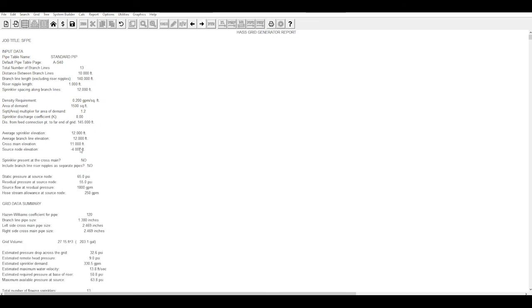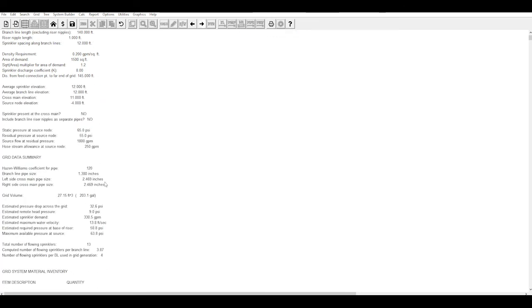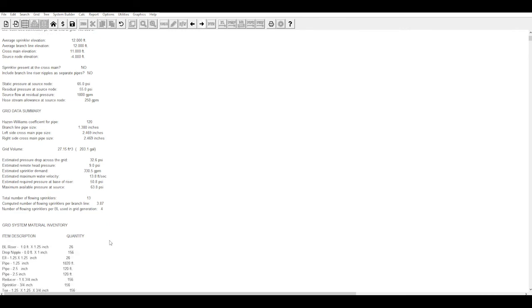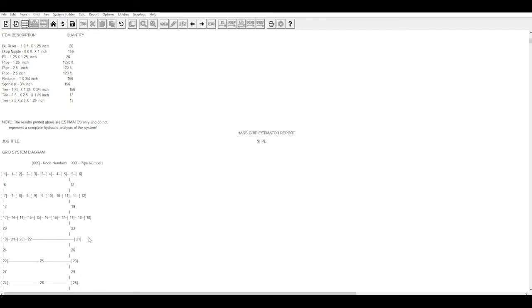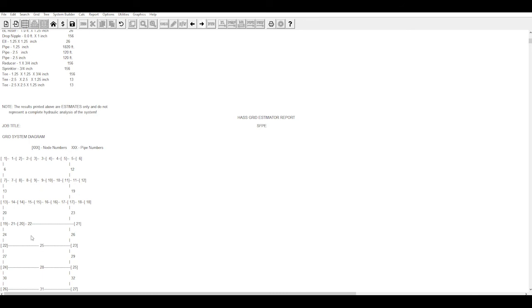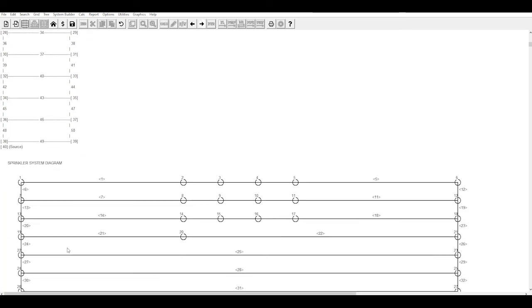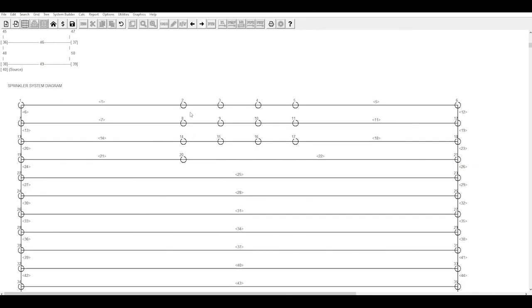So here's all that data that we entered. You can verify here again. The data that it's using to calculate. See here it also calculated out 13 sprinklers. 3.87 per branch line. So four per branch line. Then it gives you an item breakdown. And then we supply this little graph here. So you can verify that everything looks good. There's our sprinklers right there. Connecting to our cross mains. There's an actual graphical layout. So you can see here all 13 sprinklers, where they are on the branch lines.